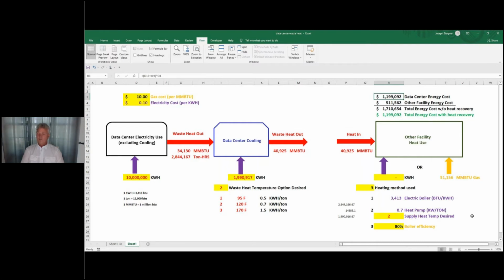Maybe Stanford will do that sometime. The reason we didn't was initially the land value around Palo Alto — they didn't want to give up space to build a commercial laundry facility on campus that could utilize this extra $500,000 to $1 million a year worth of waste heat we were throwing away, even after recovering and using everything we could. But the point is, if you have a data center where land is cheap, you might ask a laundry service provider, hey, build a commercial laundry facility right next to my data center, and I'll share the energy savings with you.